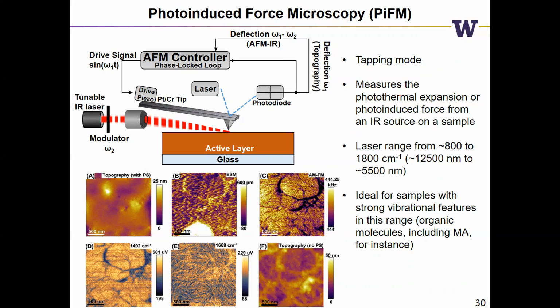In this case, it measures the photothermal expansion or the photoinduced force, depending on who you talk to, from an IR source on a sample. By IR, I mean that the laser ranges from 800 to 1800 inverse centimeters, so something like 12.5 microns to 5.5 microns, give or take. In some sense, it's like a nanoscale FTIR measurement. You don't exactly get the same spectra as you do in FTIR, but you should get reasonably close. It's ideal for samples with really strong vibrational features in this range. That's organic molecules, and that includes methylammonium or formamidinium, for example. Inorganic components you probably won't see because they generally fall outside this range.